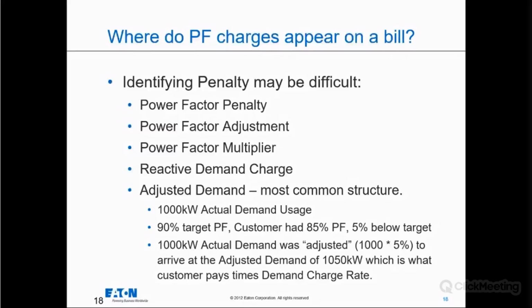Well, let's say a customer had an actual demand usage of 1,000 kW. The utility said, I want you to maintain a 90% power factor. The customer, though, was only maintaining power factor at 85% or 0.85. So they're 5% below where the utility wants them to be. So what happens on their bill? They take the 1,000 kW of actual demand and adjust it by the 5% you're below their target, and they arrive at an adjusted demand of 1,050 kW, which is what the customer pays times their demand charge rate. So you can see clearly from here that they're paying 50 kW of demand that they do not have to pay if they would correct their power factor.